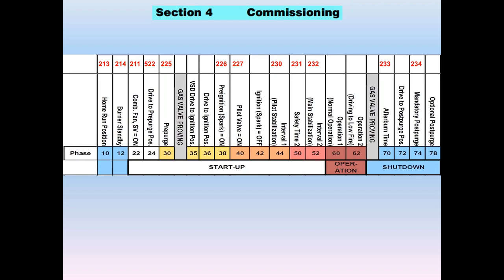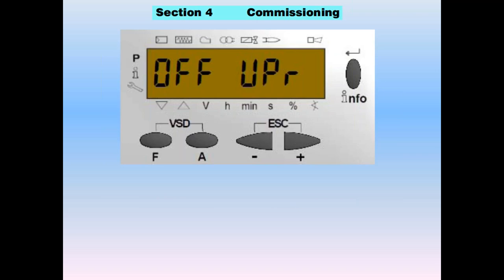Throughout the LMV3, there are phases — just like the LMV5 and all Siemens products. In blue, you see standby. The 30s are pre-purge, 40s are pilots, 50s are mains, 60s are runs, and 70 is shutdown. Each phase has a parameter associated with it. For fuel zero gas: parameter 213 sets the length of the home run phase, parameter 214 lets you clear an air pressure switch during standby, and parameter 225 sets the length of your pre-purge. All these parameters are set during the commissioning process.